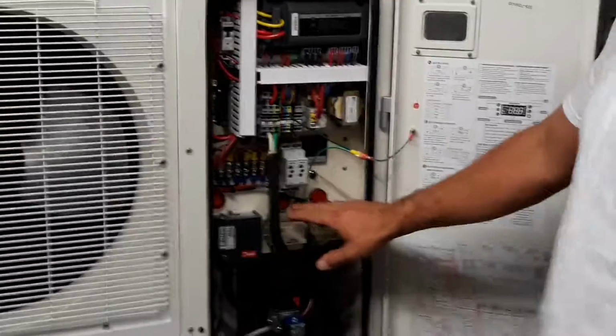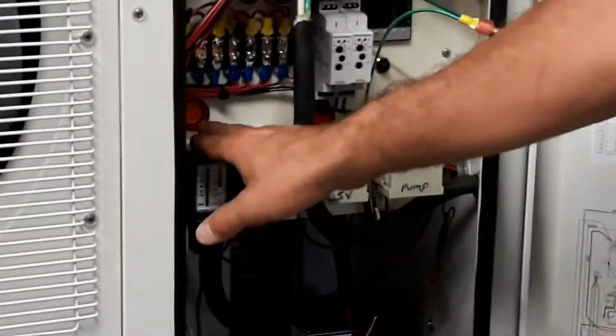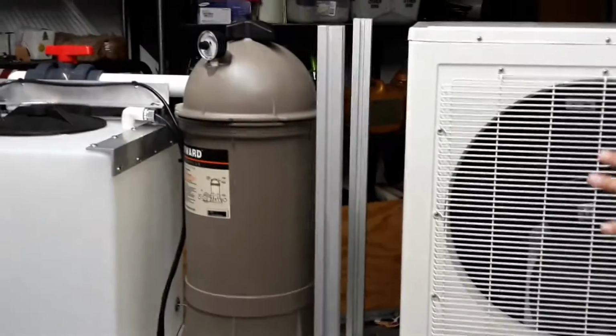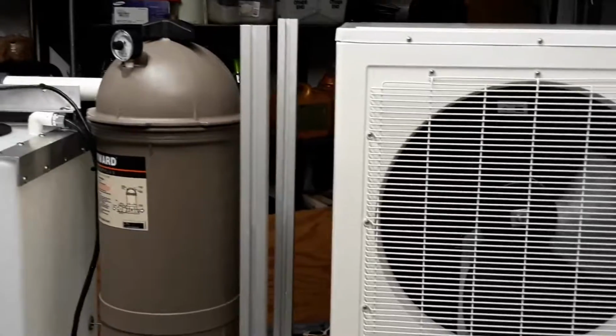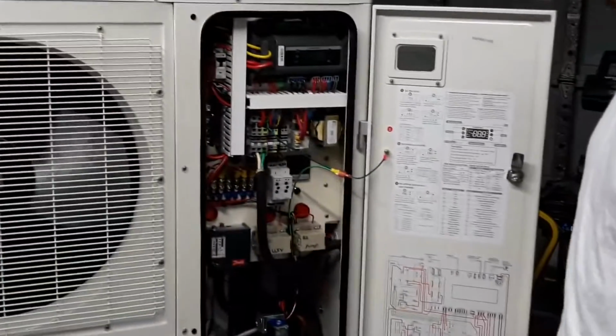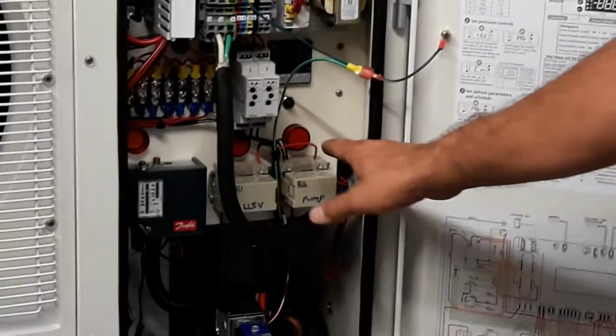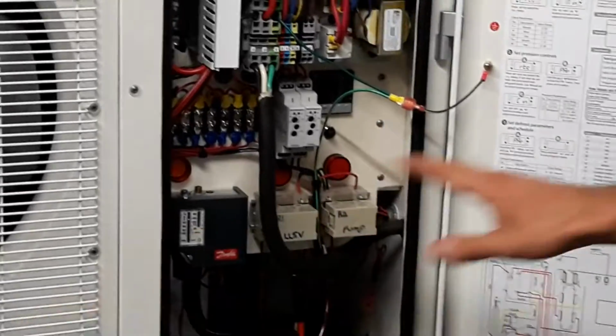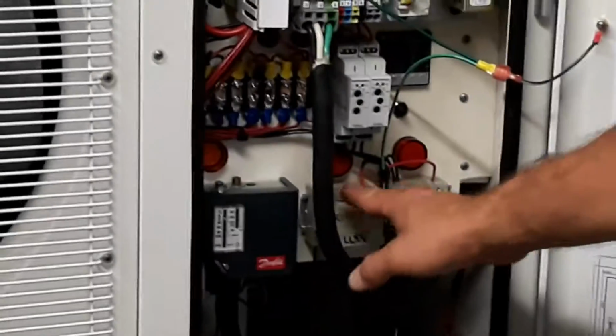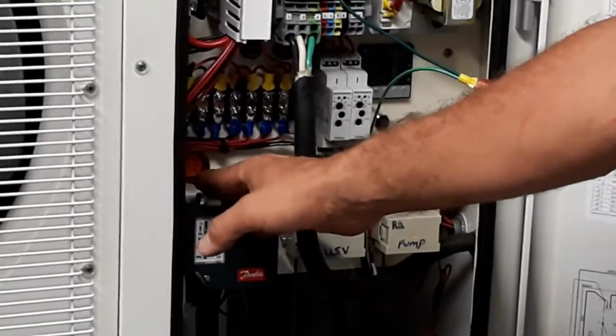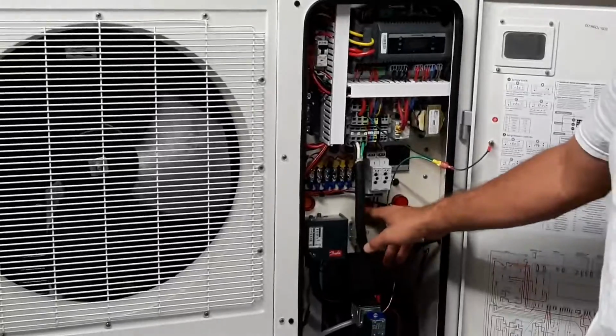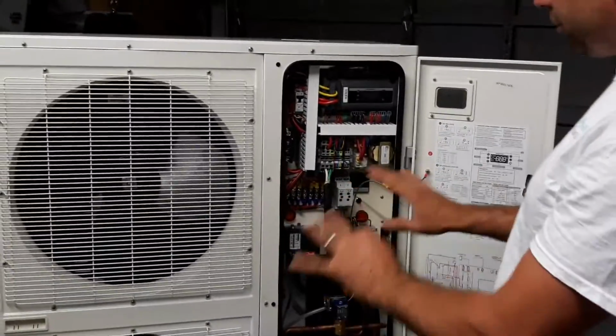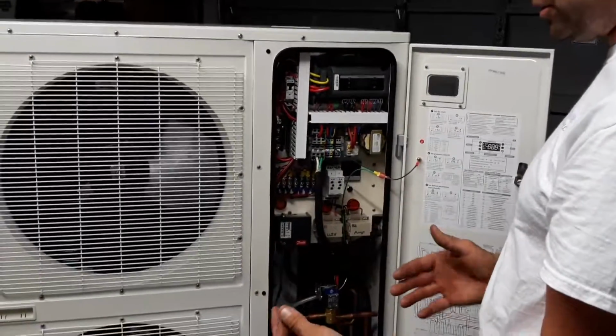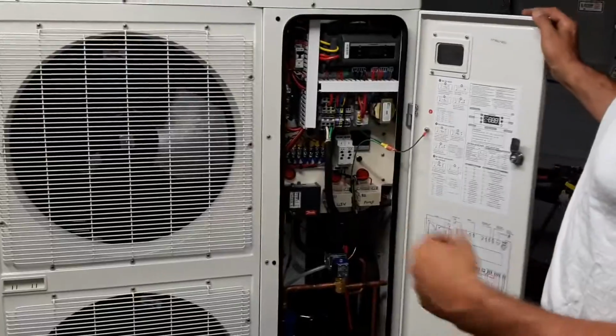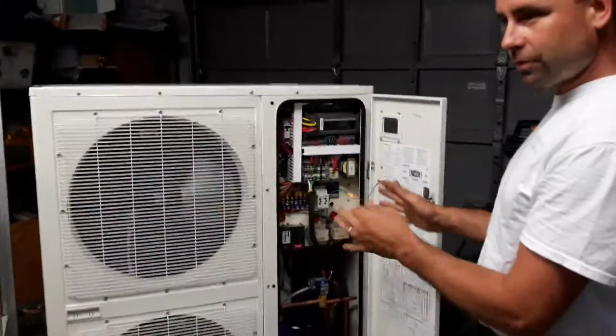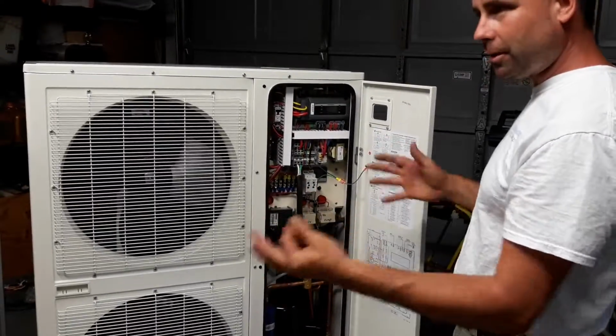We get several relays, we get some lights, indicators for clean your filter housing over there. When it becomes contaminated and pressure rises, this will illuminate and tell you to clean your filter. And then we have additional safeties with loss of water would be illuminated and shut everything off. And then we have loss of flow, which if you were to neglect your filter and flow was to be reduced, then it would illuminate and shut off the refrigeration system so you don't end up with a freeze-up condition and damage your heat exchanger. So if there's a failure and you were to enter, it would tell you specifically kind of where to look in order to repair the machine and get it back and running.